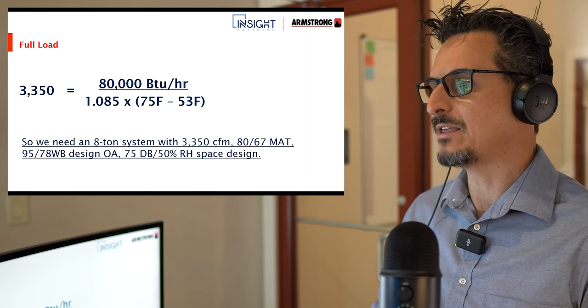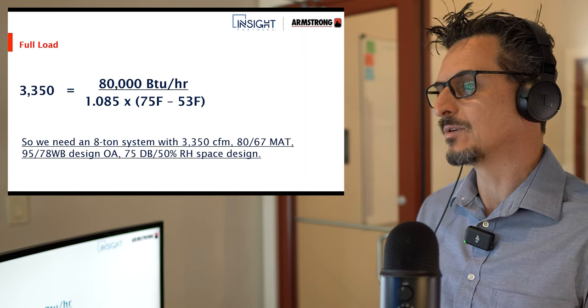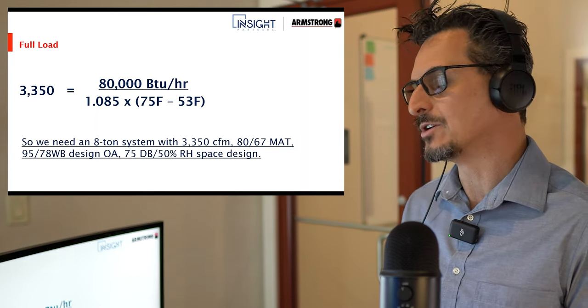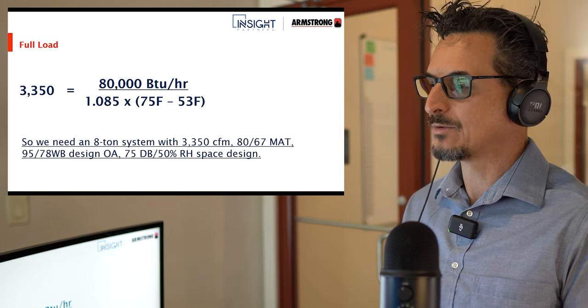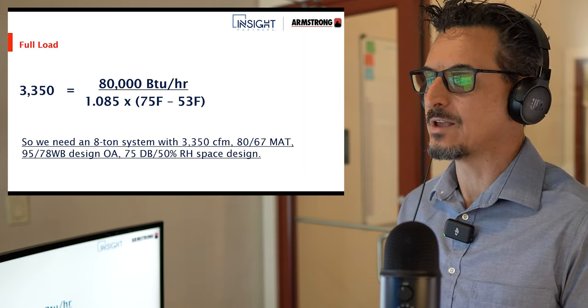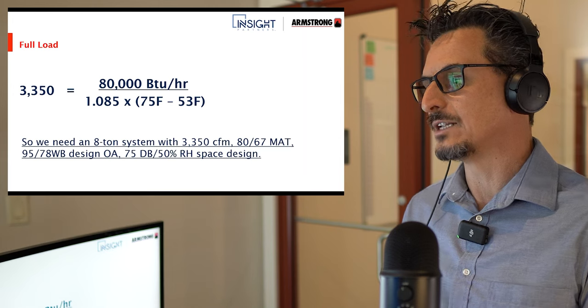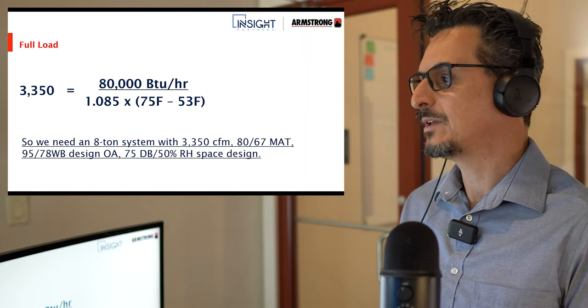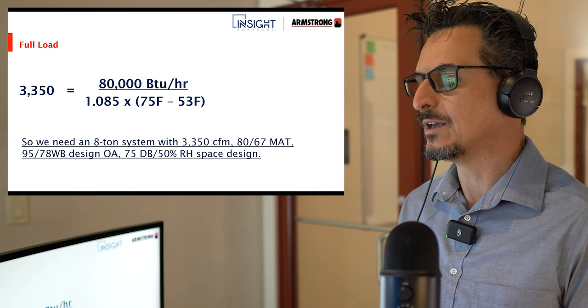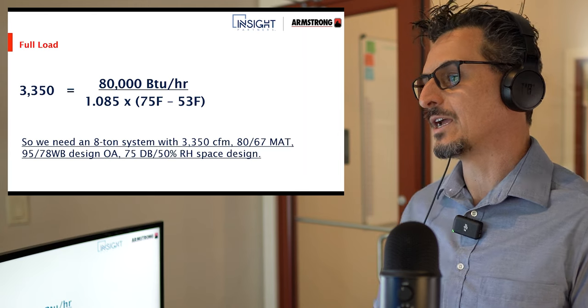At full load we have 80,000 = 1.085 × CFM × (75 − 53). We're going to start with a 53-degree supply temperature, which is where the unit probably should be. That gives us a 3,350 CFM system. So we need an 8-ton system, 3,350 CFM, 80/67 mixed air temperature, 95/78 wet bulb for the design outdoor condition — a nice steamy, sweltery day — and a 75°F dry bulb, 50% RH space condition.